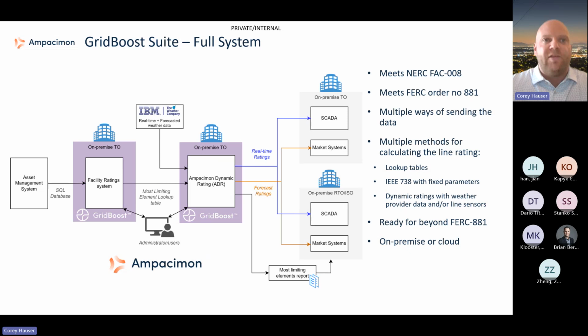So there are ways the system can be customized to fit your specific needs or environmental conditions. As a whole, with these solutions combined, you can meet NERC FAC 08 compliance and FERC 881 compliance. There are various methodologies you can use and choose from in the systems, even creating your own, or just using linear fixed rating systems. It really gets you set up for not only FERC 881, but allows for that next step into DLR. One final thing to note: these systems can be cloud-based or on-prem, and we can integrate them into your EMS system. It really creates that entire end-to-end solution, going from facilities to EMS to market systems, all intertwined, if that's what you're looking for.